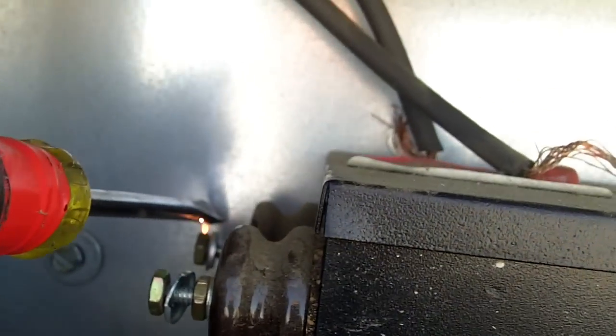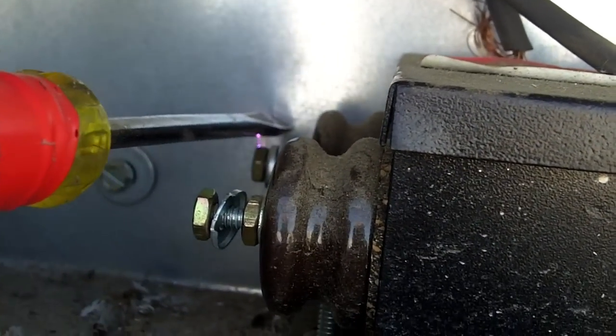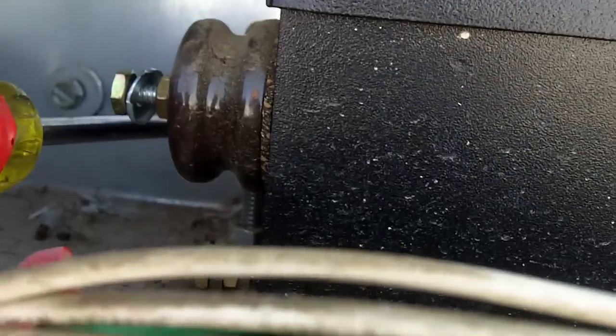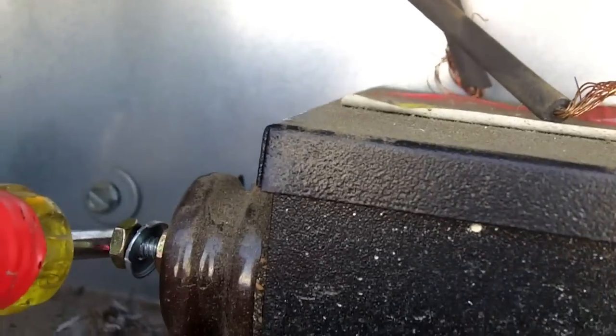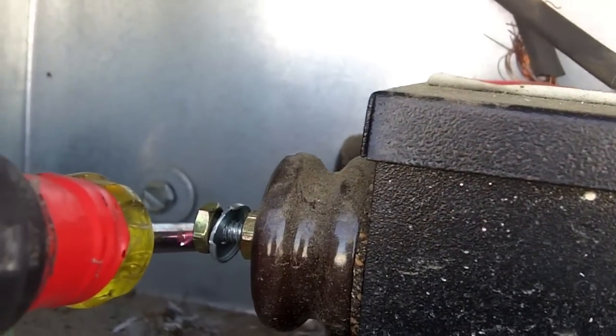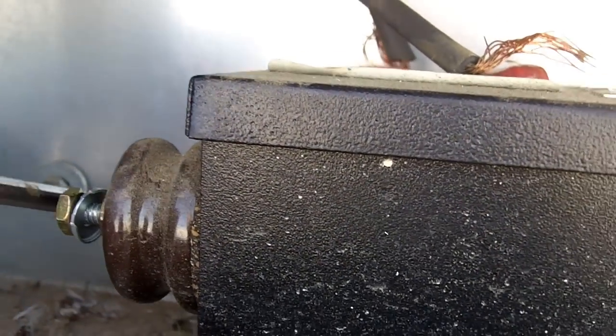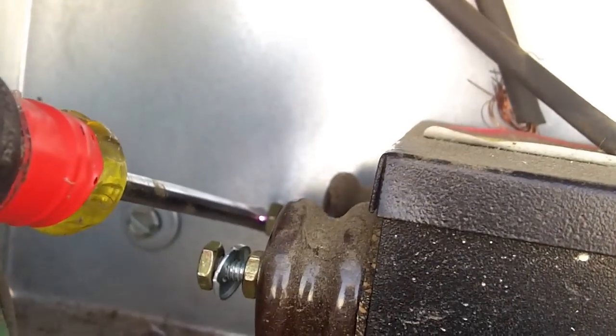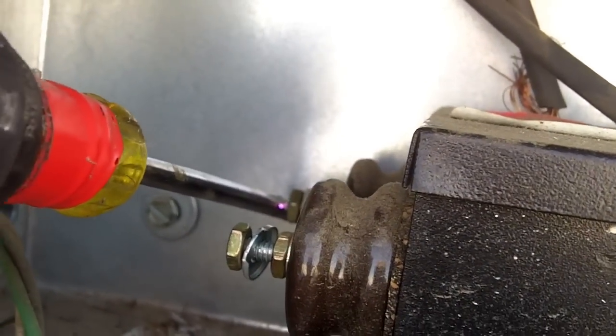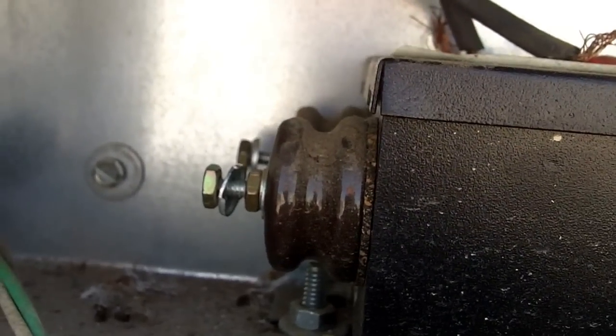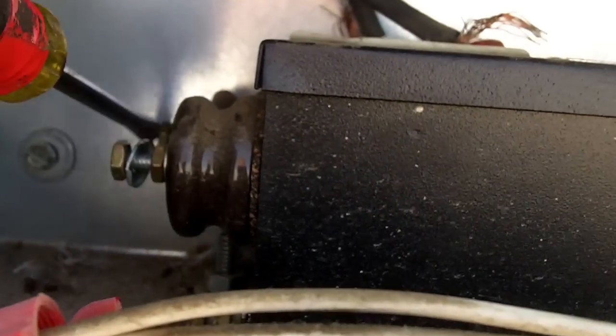Now watch this, see that arc? This is a smaller transformer, so the arc's not as big, but you can definitely see it. So that's telling you that this neon transformer is putting out power, so it's a good transformer. That is how you test a neon transformer.